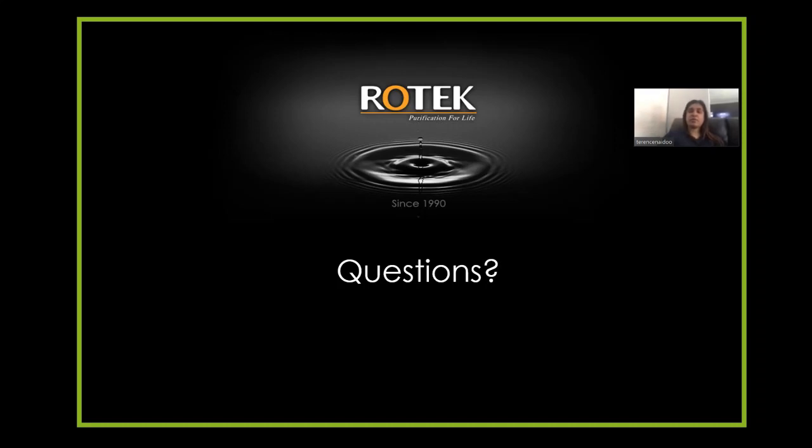Cool. And our problem in South Africa is mostly scale, and scale is your cations and your anions. It's only until a few years ago that we actually introduced analysis of silica in water, because people didn't know what silica was actually doing. That's right, normally we talk about calcium and magnesium. Now we have something that's going to assist with this, because silica really cannot be removed out of water. Avista is your middleman, with the correct calculation as well.